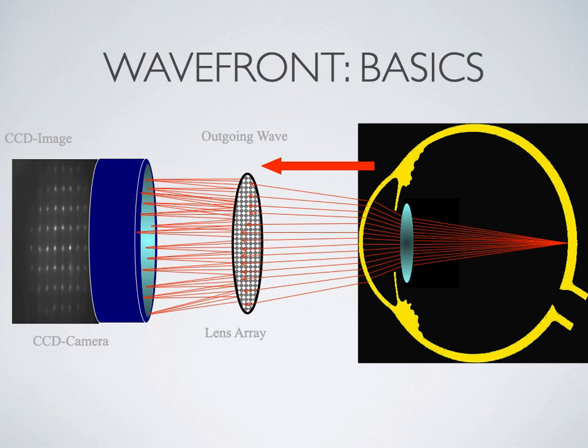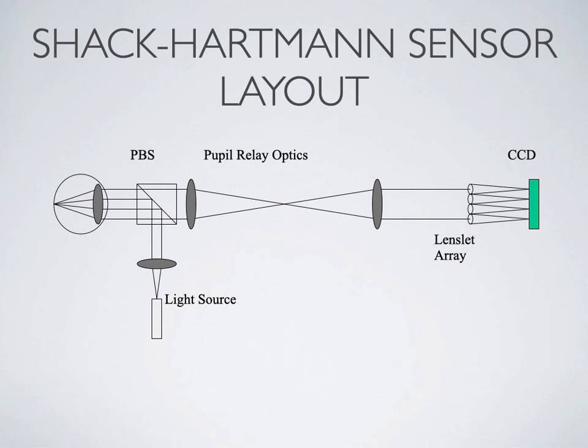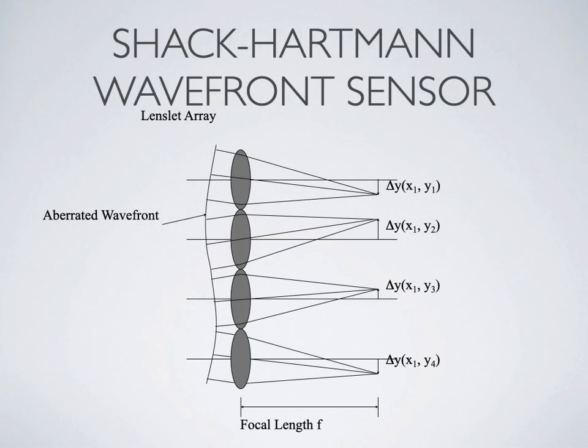We can quantify things with a Shack-Hartmann aberrometer. Rays of light emerge from the patient's eye and pass through a grid. The spacing of the dots produced by the grid gives us information about the shape of the wavefront. The grid has little lenslets that focus onto a CCD chip, which looks for the locations of the dots. With an aberrated wavefront, the dots will be all askew.